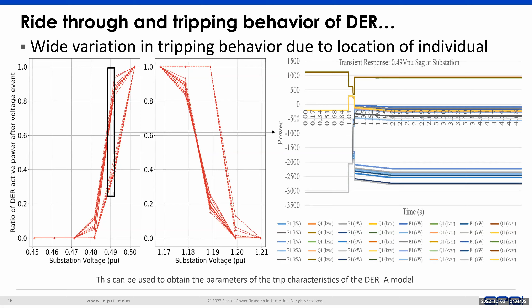We then used that to determine the generalization approach. What we essentially say is that the first inverter to trip on a system is likely located towards the tail end of the feeder, because that's where you have the largest voltage drop most times. The last inverter to trip was likely located towards the head of the feeder. It's all kind of intuitive when you look at it.